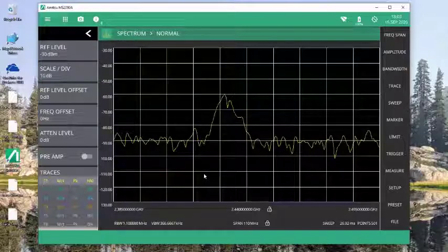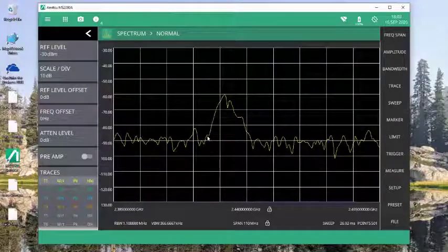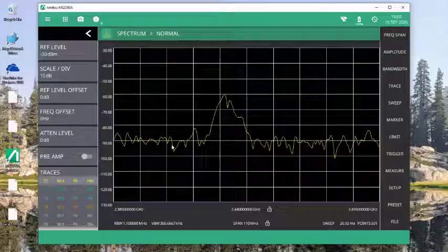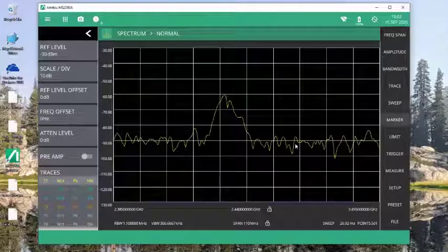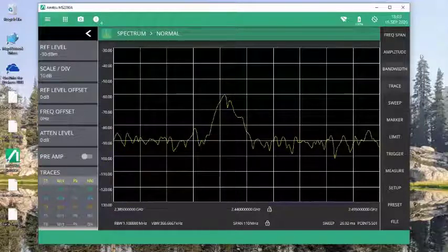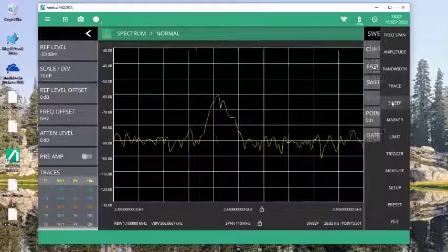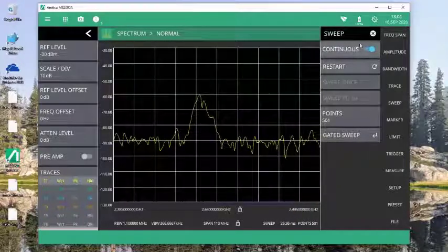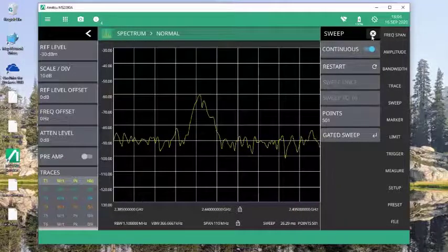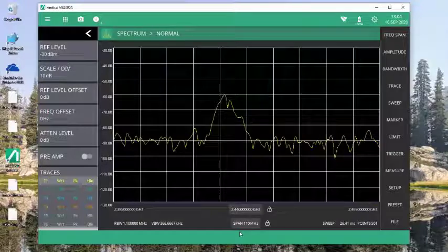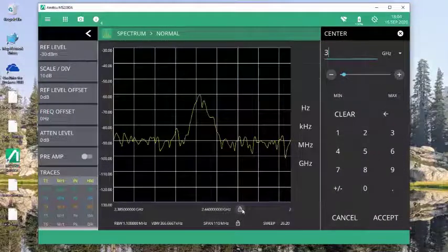So I also want to point out that once you've recalled a trace into a hold mode, it's critical that we don't display erroneous data on the screen.